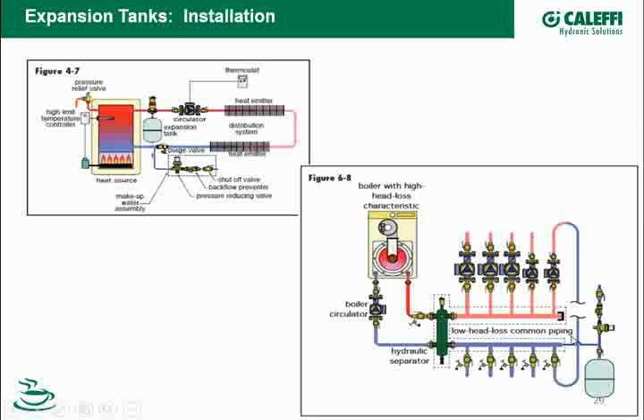Now, you'll notice that my expansion tank is actually tied in on this drawing all the way to the end of my low-loss common piping. If I am sizing that header pipe properly, there's very little pressure drop across it, and I like to use this picture because it gives me design freedom. I can put it on the end of this header pipe here, or I could place it anywhere around my hydraulic separator, anywhere I need that expansion tank from a room type standpoint.